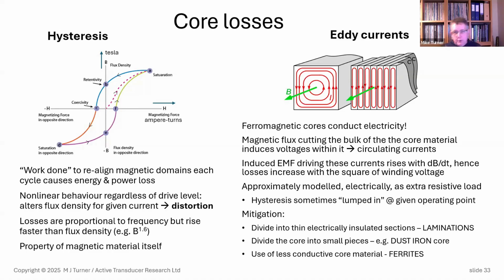That gets worse. The point about skin effect gets worse as you wind the coil up into a tight bundle in a transformer, because not only do those conductors have their own self-induced magnetic field in them, they've got field from all the other conductors that are next to them. And so you get induced losses in the bulk of the conductors, and it's sometimes called proximity effect. It's a very big deal in things like power transformers.